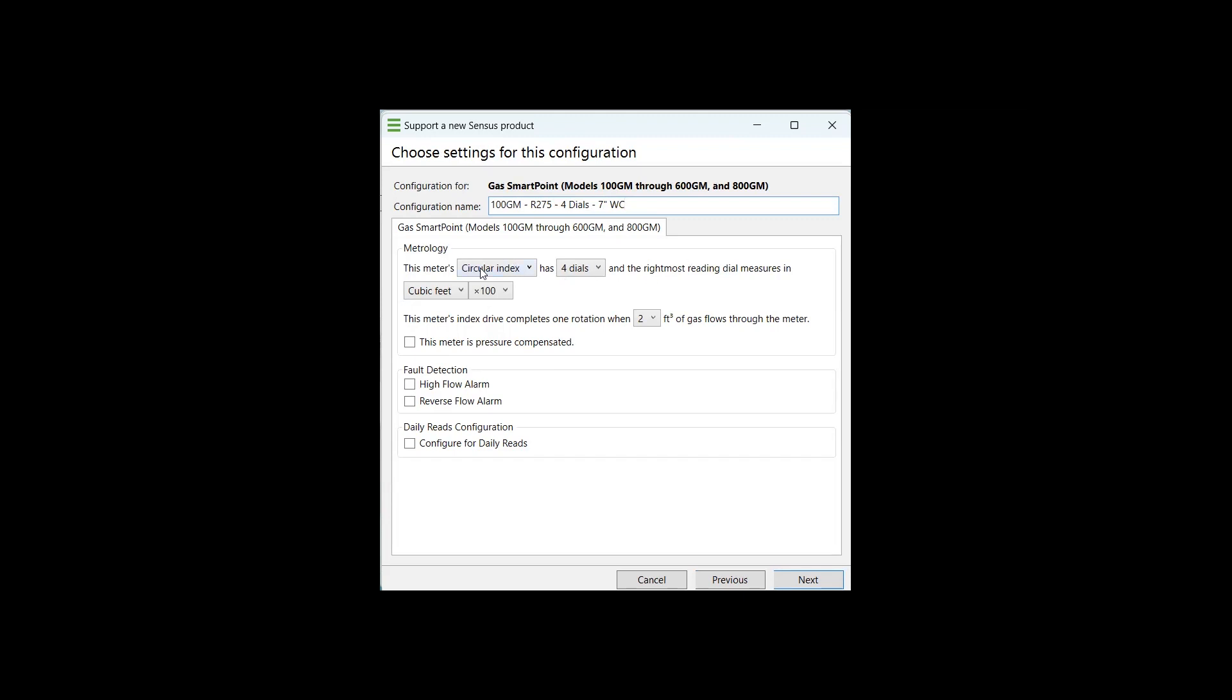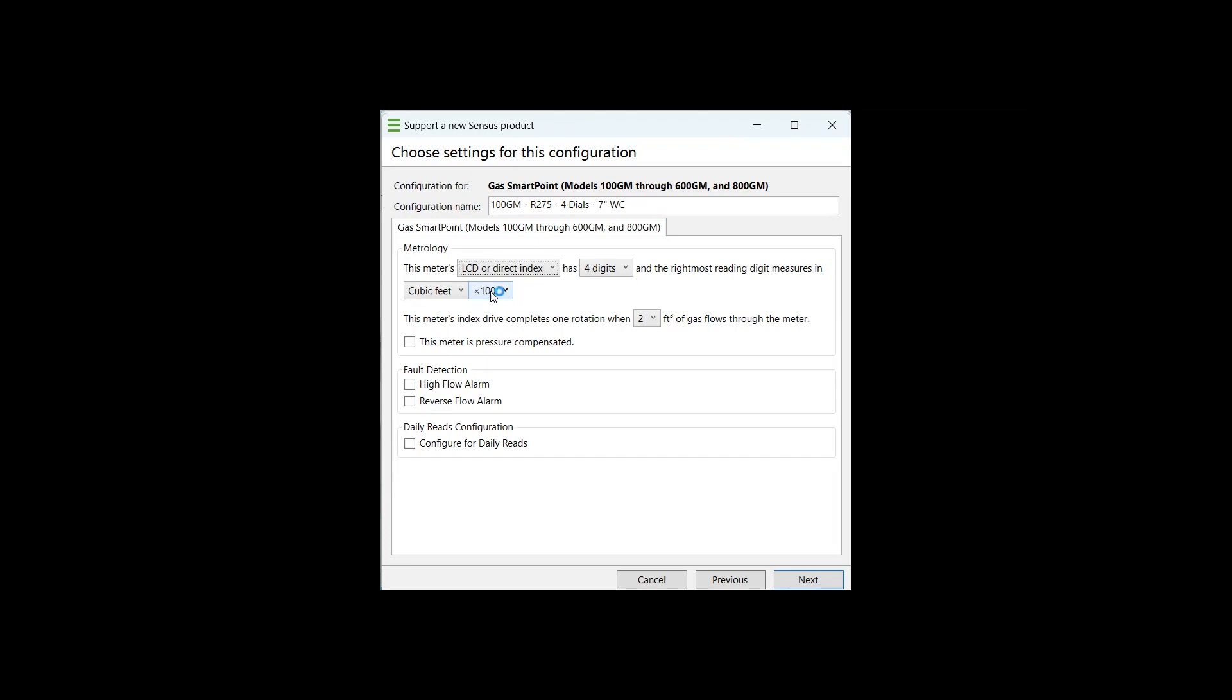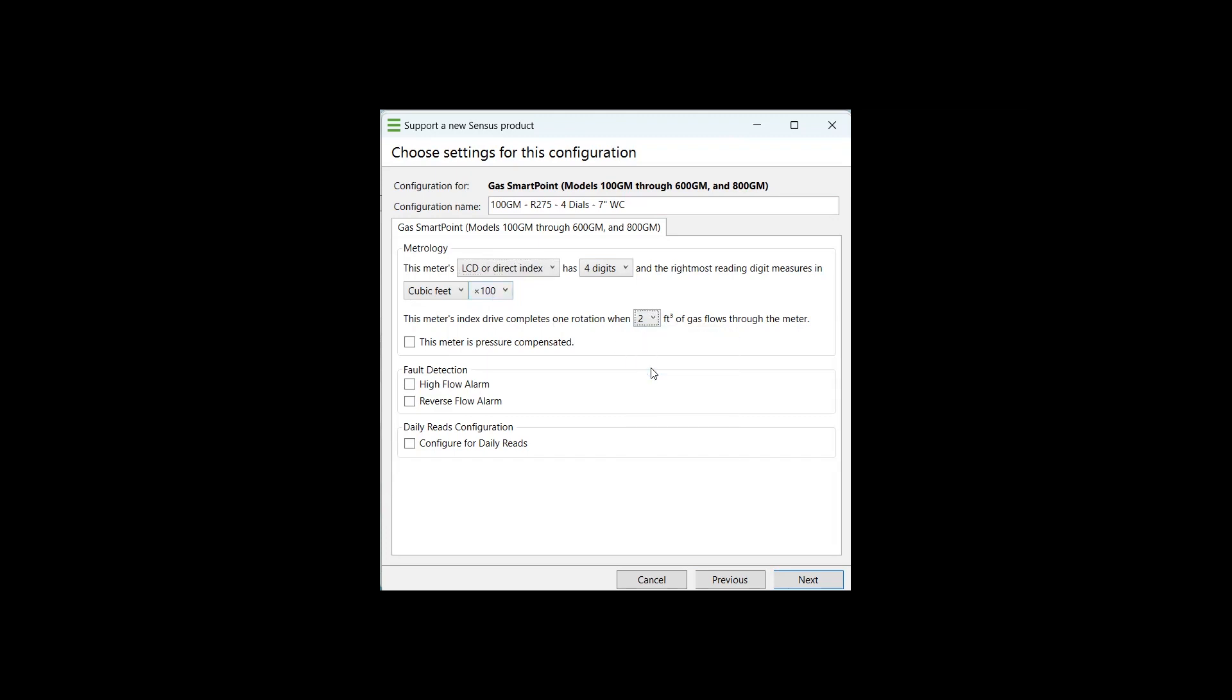The next thing we're going to do is select the type, select the correct parameters for the index that you have in front of you. This particular index that we're looking at on an R275 has an LCD or direct read index. It has a direct read index with four digits. The right most reading digit on those direct read dials measures in cubic feet at 100 cubic feet as the multiplier. The census R275s have a proving hand of two feet, which is the small dial in the bottom left hand corner of your index. So we will select two feet.